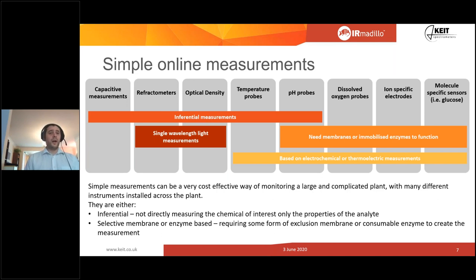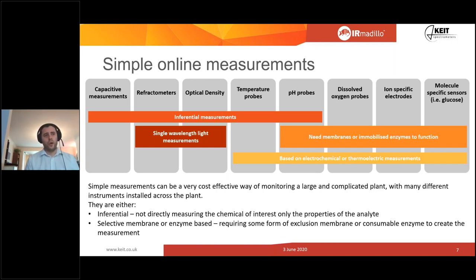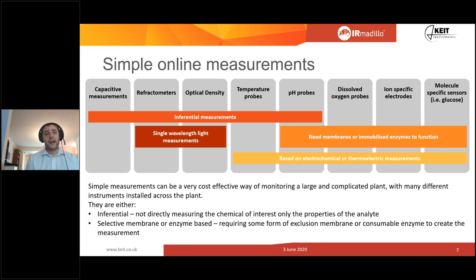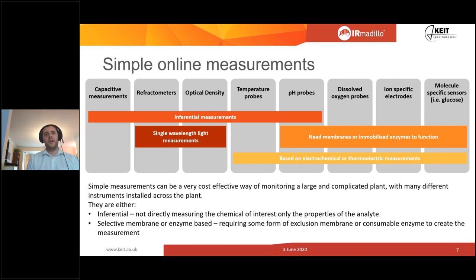There are quite a lot of simple online measurements that customers tend to have installed on their processes already. Capacitive measurements are electrical sensors that sit in the process — very good for biotech looking at cell growth, but not so good for oil processing. Refractometers use a single wavelength of light to look at refractive index. For example, water dissolved in edible oils could be done with a refractometer, but the process needs to be at an exact temperature because refractive index changes with both water content and temperature, and you can't distinguish between the two causes.